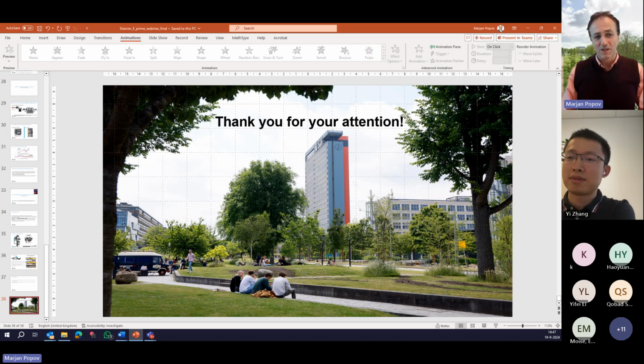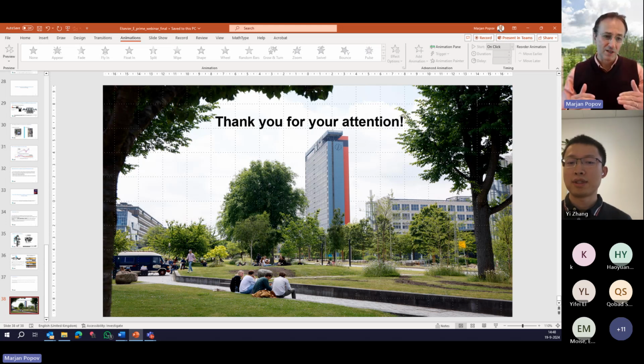However, the problem that we found was exactly what I have presented here. The form and envelope of the fault current in this case is very different from that resulting from synchronous generators. If you have a type 4 converter, then you have a prompt rise of the fault current, which is later removed. Practically, the relay does not have time to detect the fault. My experience is that we decreased the fault detection threshold to the minimum. At one point, for some relays, I cannot say which one because this project is protected until 2025, we experienced that the fault would not be detected.